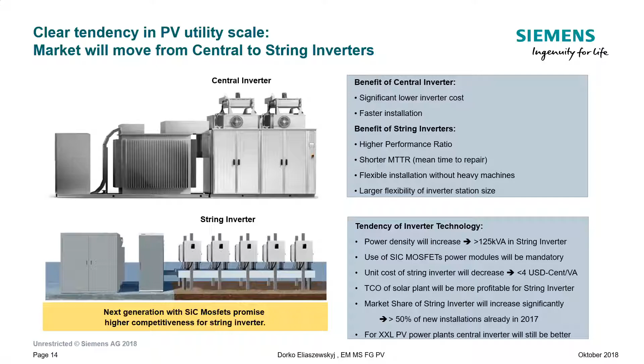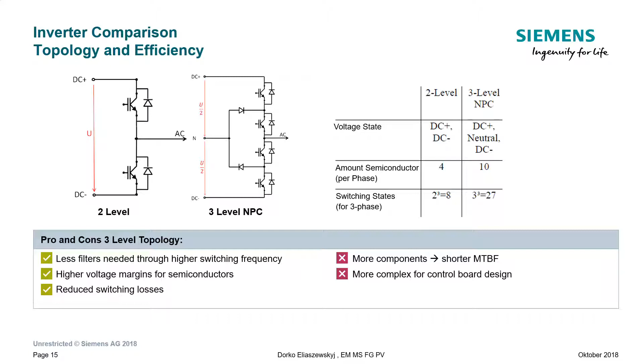A little more technical, if you allow me: 2-level, 3-level, today we are speaking only about 1500 volts in the PV area. I still see here and there, for example in Taiwan, I recently got a request for a 1000 volt PV power plant, but this is not what we see in general. In general, we see 1500 volts, and if you go to 1500 volts, then you have to go to a 3-level inverter. Please take care with this IGBT solution, otherwise you will fail.